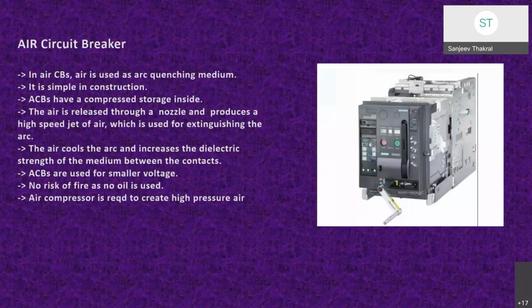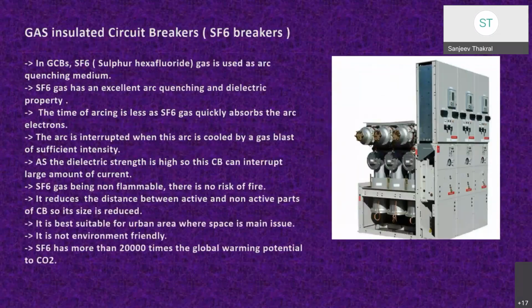In air circuit breakers, air is used as the arc quenching medium. It is simple in construction and has compressed air storage inside. Here the air is released through a nozzle and produces a high-speed jet of air, which is used for extinguishing the arc. ACBs are used for smaller voltages. There is no risk of fire as no oil is used. The disadvantage is that an air compressor is required to create the high pressure air.